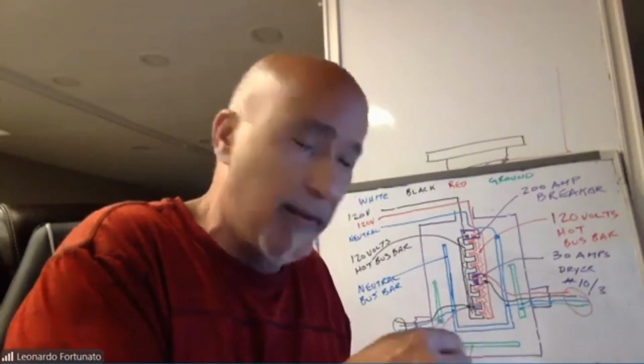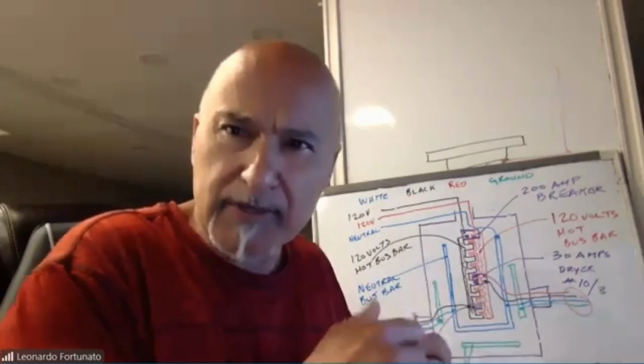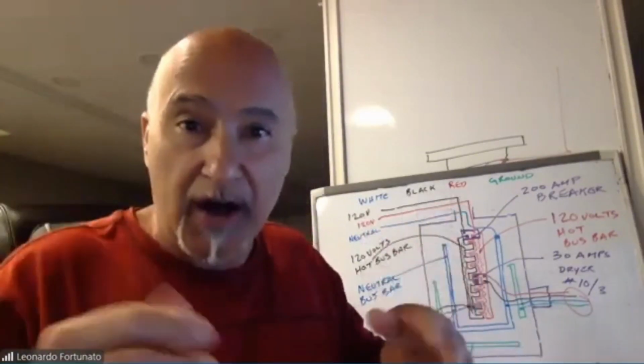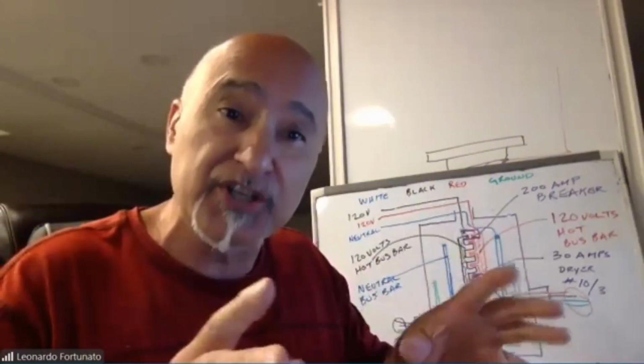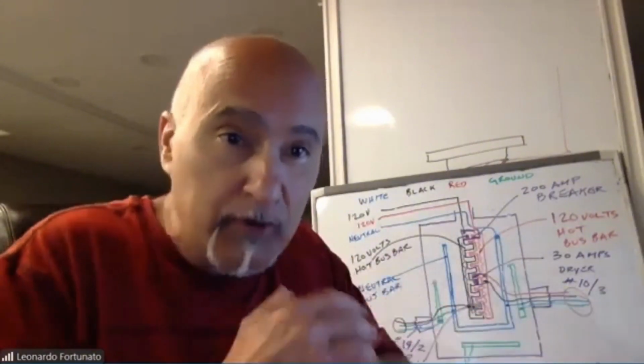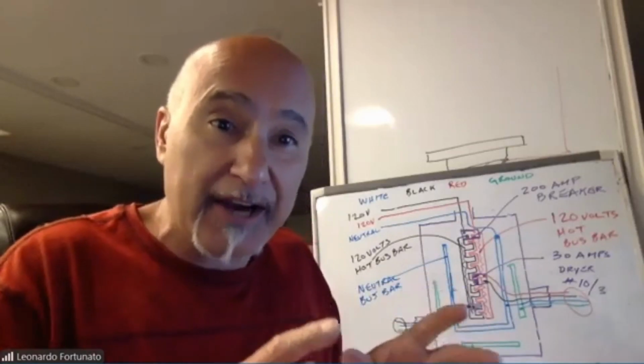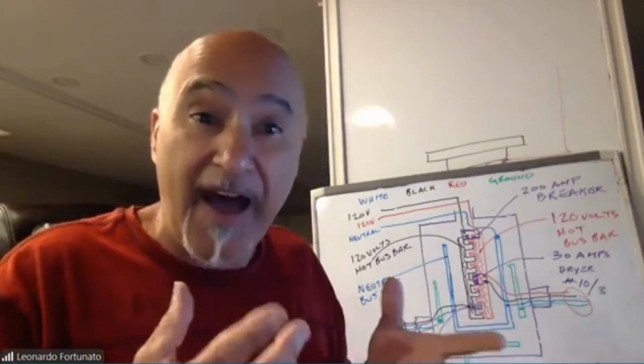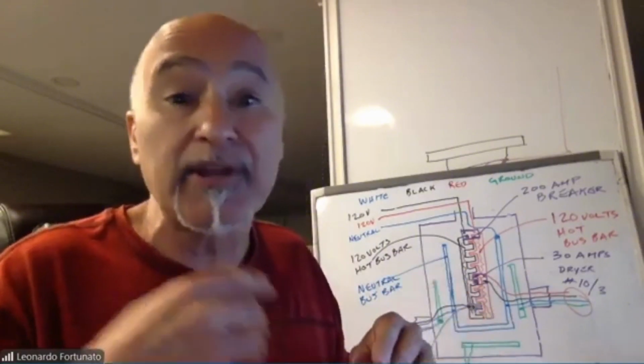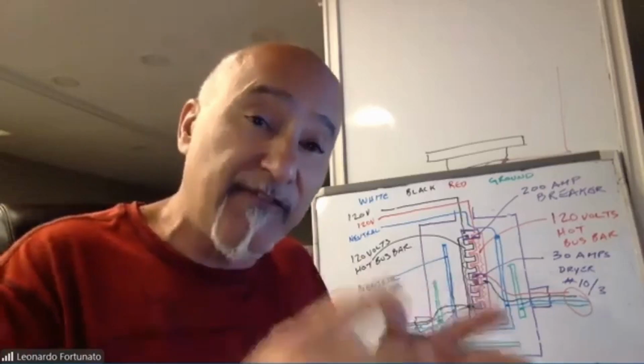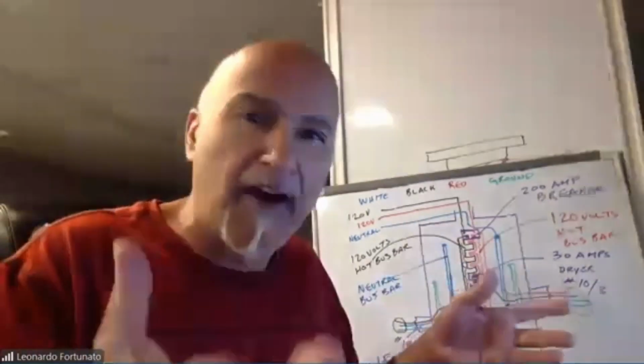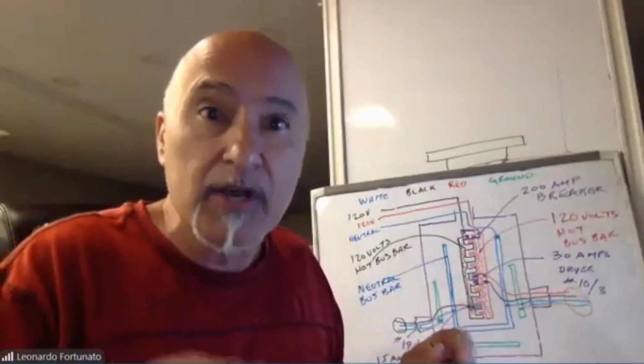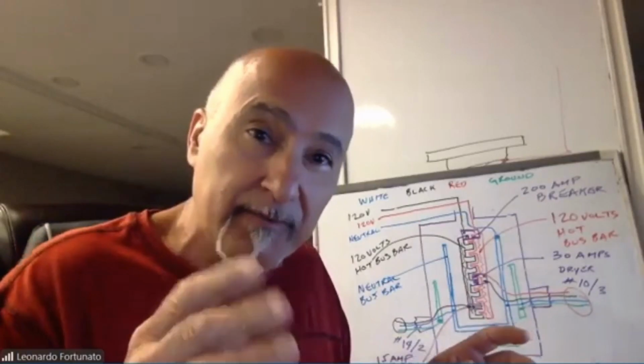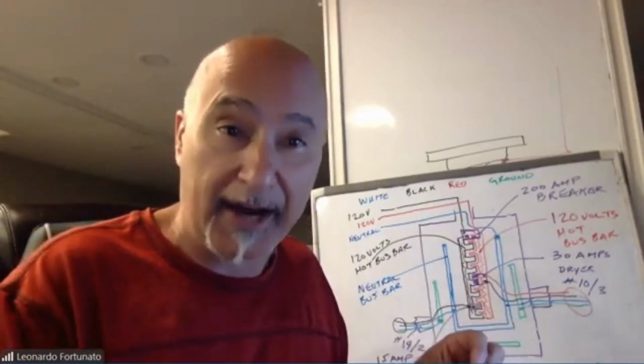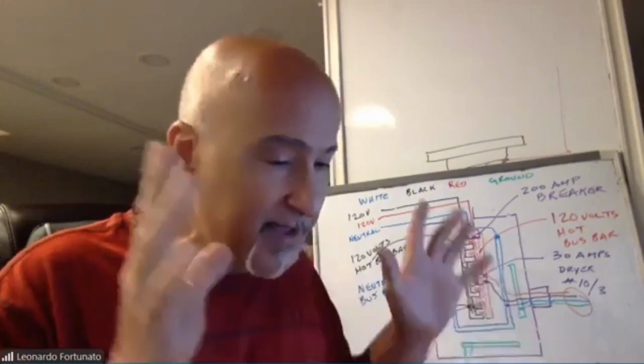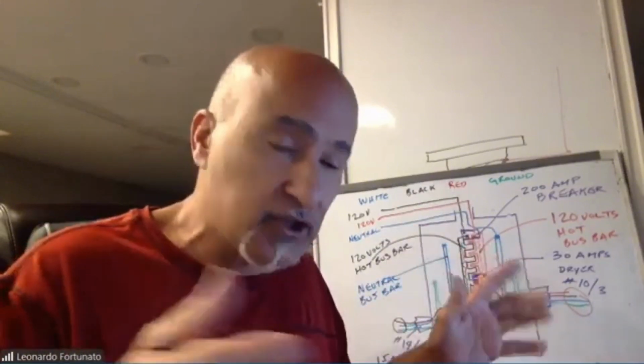Another very important thing: when we make electrical connections, for example adding onto a house, never ever bury connections inside a wall, because if they become loose, nobody will find them. Whenever I make connections, I like to do it in a box where there's a light fixture or something functional, so I don't end up with a blank cover plate in the middle of nowhere. But sometimes it happens, and we always want a plate we can remove to expose that box and check our connections. Never bury anything in a wall. It's a fire hazard, and if anything is loose, we'll never find it.